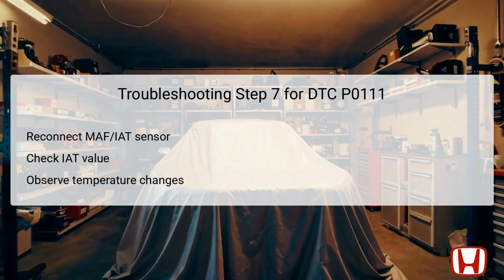In this step, you're looking for a significant change of 63 degrees Fahrenheit, 35 degrees Celsius or more. A response of this magnitude indicates that the sensor is functioning well at this moment, suggesting an intermittent failure. If the sensor does not respond appropriately, it is likely malfunctioning, and further investigation or replacement would be warranted.